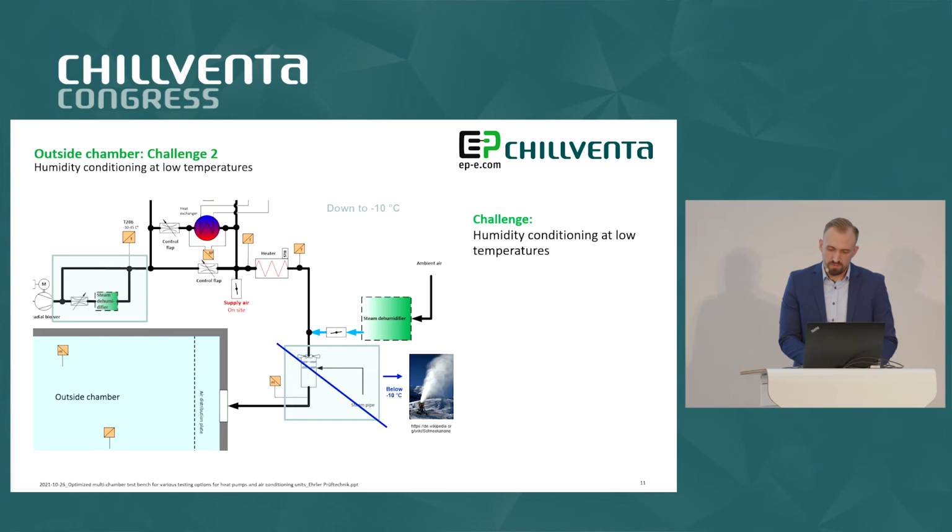The introduction of the humidity is done via a steam ring pipe. Introducing the humidity is particularly important in the outside chamber. The heat pump is acting in this chamber as the humidity consumer. The heat pump, as the test object, has air distributions available in the concentric circle of the test chamber.